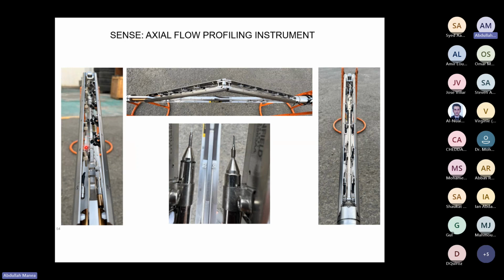With conventional probes, there's a space between them - for example, if you have one probe here and another here, there's about a 1 inch gap between the two probe tips. If the water level is in between, the bottom probe will see water and this one will see hydrocarbon, but you don't know exactly at what level between these two probes the water level is. With this new capacitance technology that covers the wellbore's vertical axis 100%, it gives you full coverage for the water holdup across the vertical axis of the pipe.